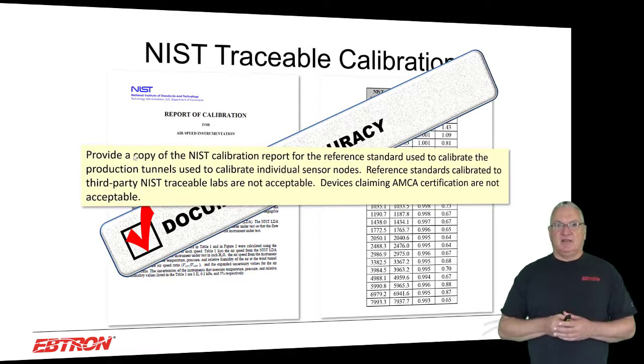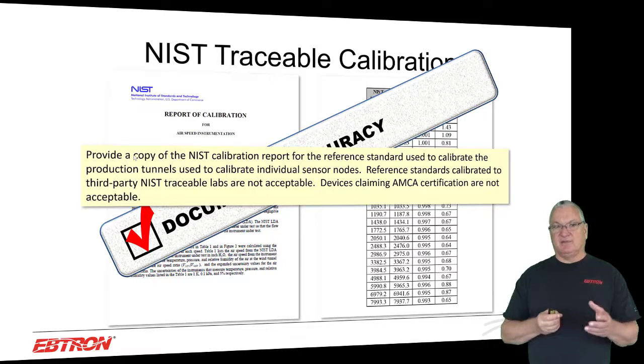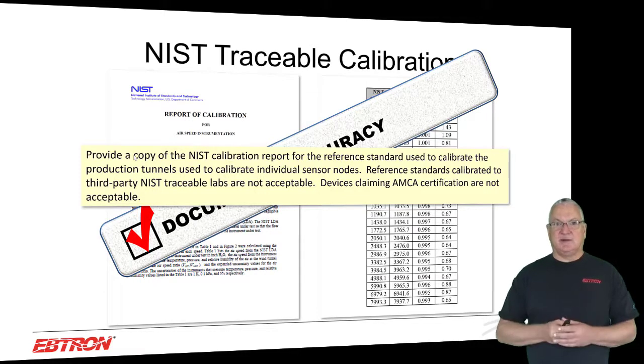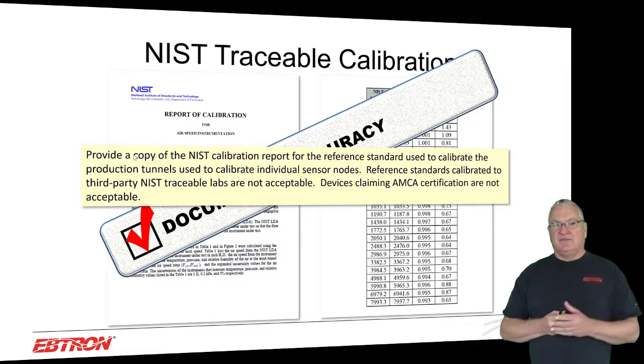We'll do something that nobody else will do that I'm aware of. Provide a copy of the NIST calibration report for the reference standard used to calibrate the production tunnels used to calibrate individual sensor nodes. Put that in your specification because nobody else is going to do that. And then reference standards calibrated by third-party NIST traceable labs are not acceptable, because why add that other level of uncertainty? And devices claiming AMCA certification are not acceptable.